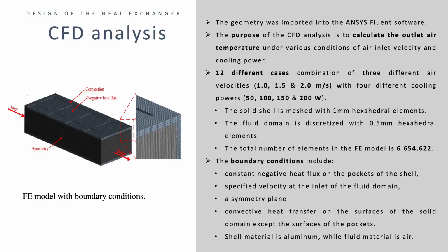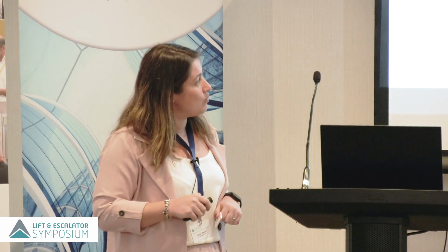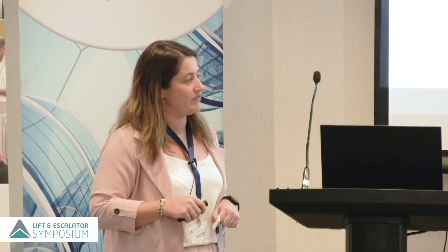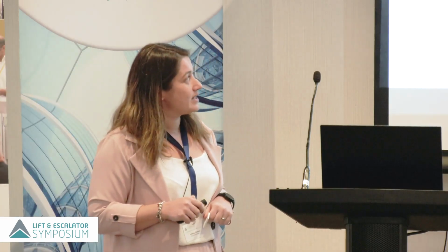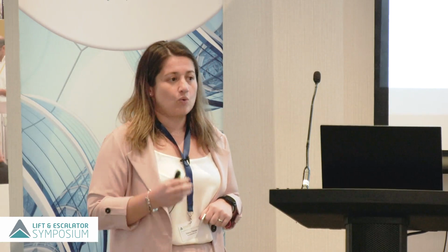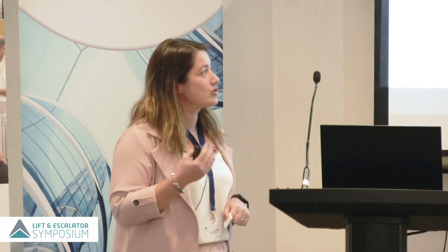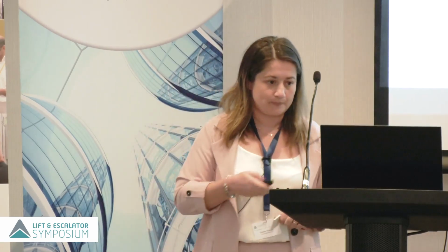And in order to simulate whether that would actually work in real life, we had some kind of computational fluid dynamics analysis. We used more than 6 million finite elements in order to do the analysis, and we had 12 different cases. Combination of 3 different air velocities and 4 different cooling powers.